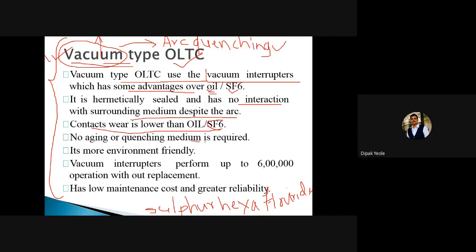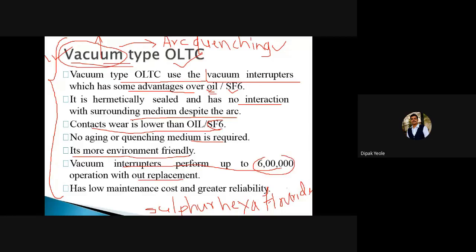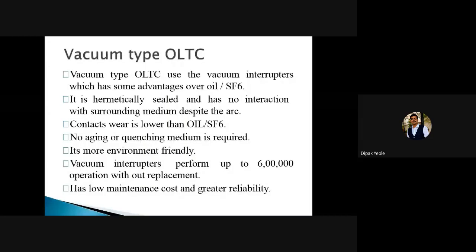Vacuum interrupters perform up to 6 lakh operations without replacement. You can see the number of operations we can perform with vacuum interrupters. The advantageous part is it has a low maintenance cost and greater reliability. As an electrical engineer, we have to maintain the reliability of power supply. If you are using advanced techniques like vacuum type OLTC, then because of this vacuum type OLTC we can ensure the reliability of our power system.